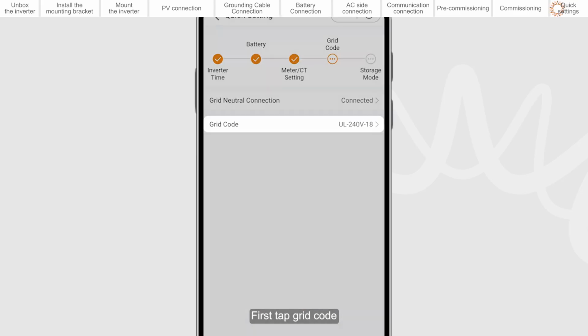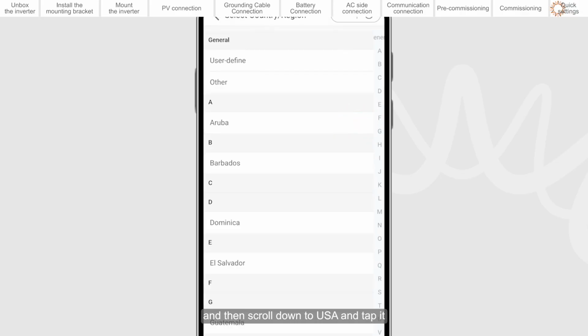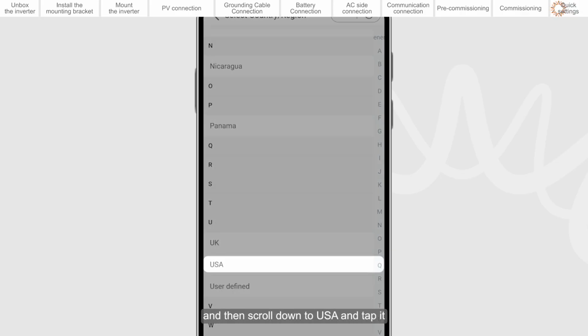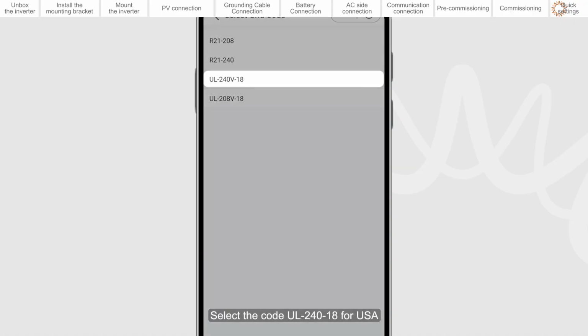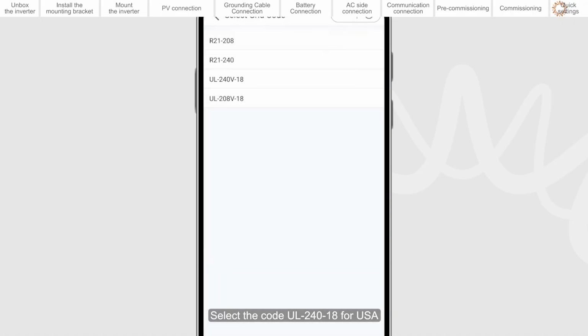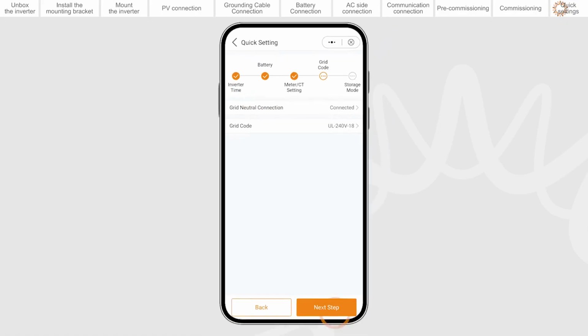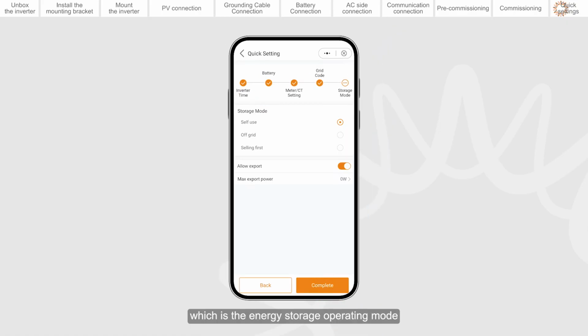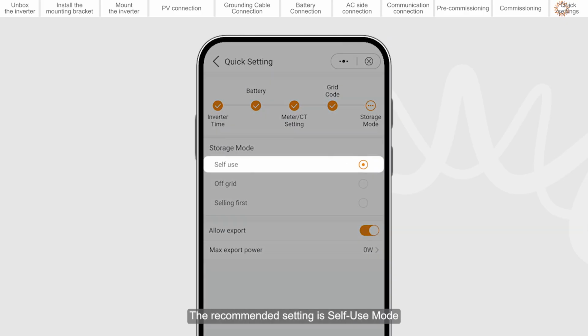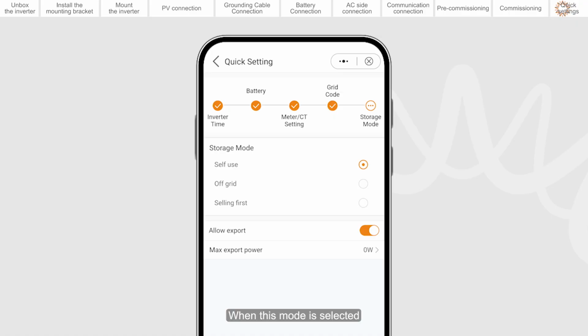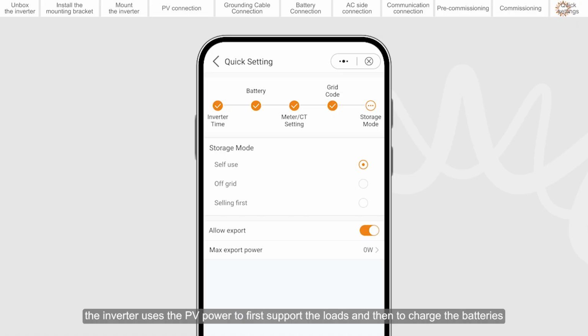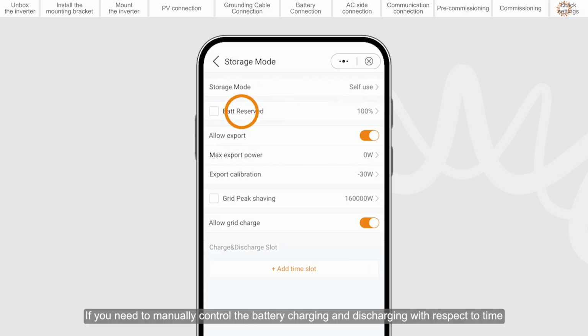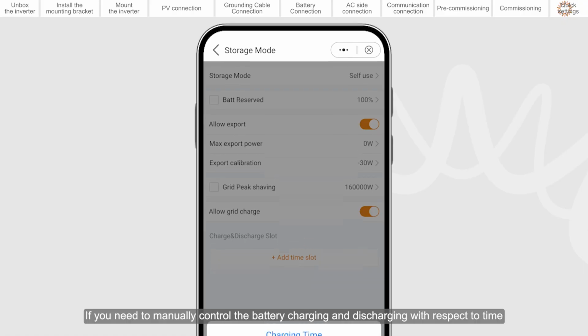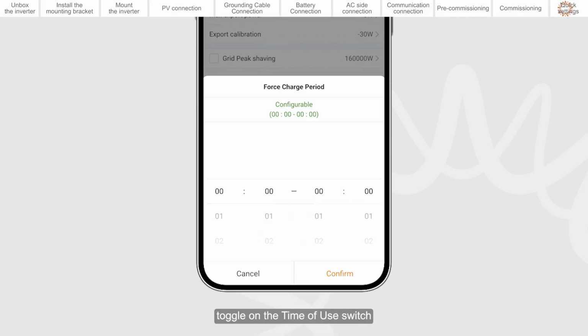Select the grid code. First tap Grid Code, and then scroll down to USA and tap it. Select the code UL 1741 for USA. Set the work mode, which is the energy storage operating mode. The recommended setting is self-use mode. When this mode is selected, the inverter uses the PV power to first support the loads and then to charge the batteries. If you need to manually control the battery charging and discharging with respect to time, toggle on the time of use switch.